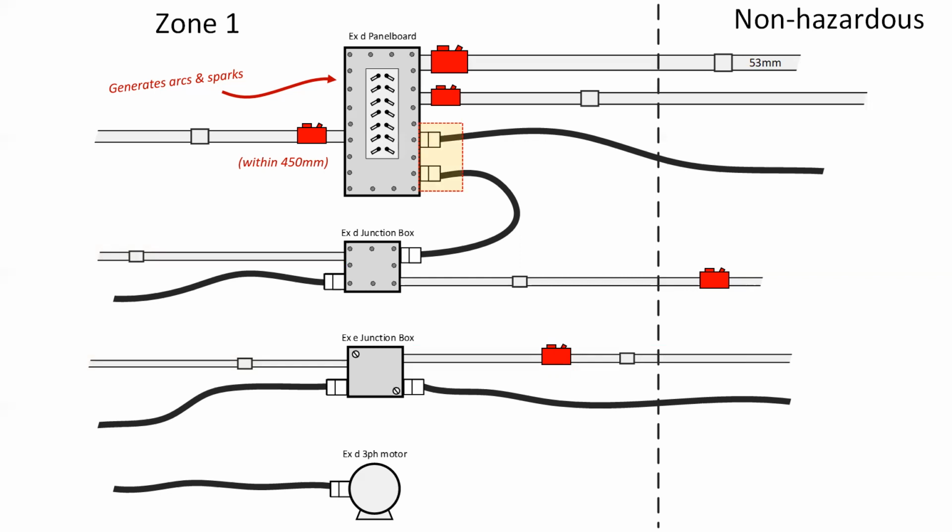The cables are going to enter into, in a few different places, explosion-proof rated enclosures and non-explosion-proof. So 18-104, when we're dealing with cables, we have two different rules which may be relevant, subrule 7 and subrule 8. Subrule 8 is indicating explosion seals are required on a cable every time they enter into an explosion-proof rated box. So these two would need to be explosion-rated seals. On these two, same idea. These are explosion-rated seals because it's an explosion-proof junction box.